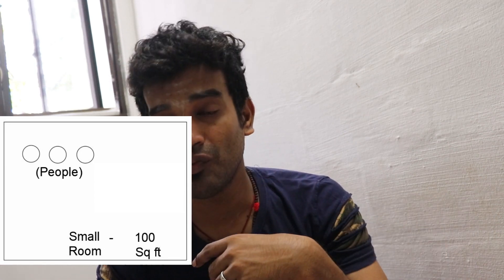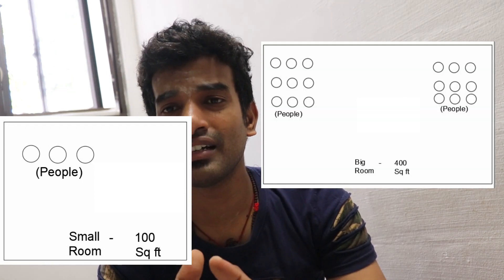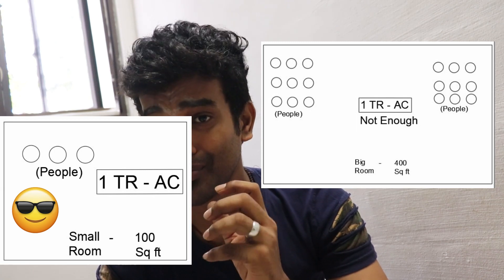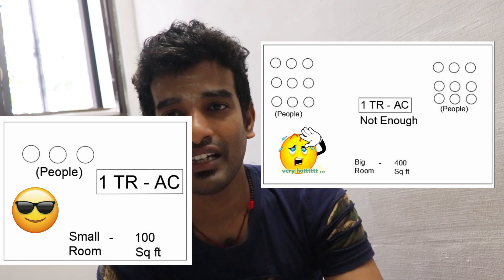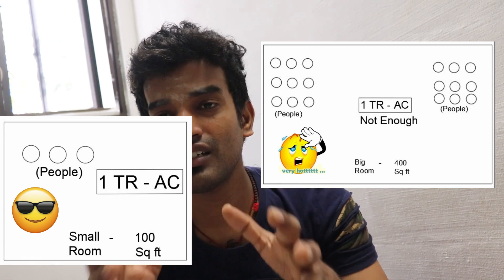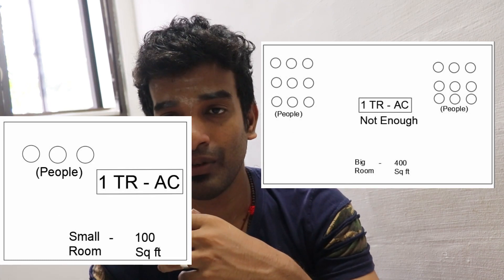Now, what is the role of a design engineer? A design engineer has to calculate the basic design — for example, how to size equipment. It is simple. If you have a small room of 10 by 10, that is 100 square feet. You take a 1-ton capacity unit. A bigger room needs more cooling, so for around 400 square feet you can use a 2-ton unit.